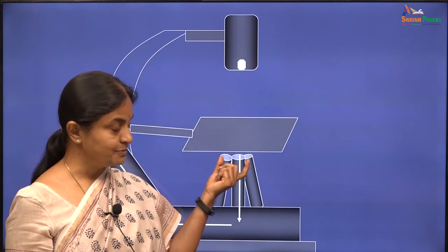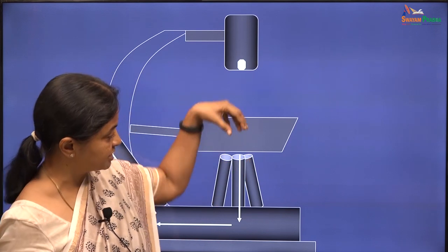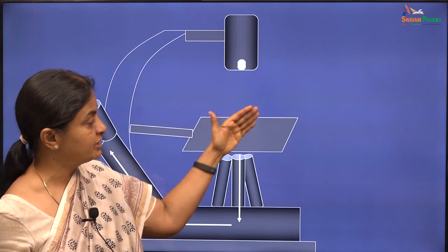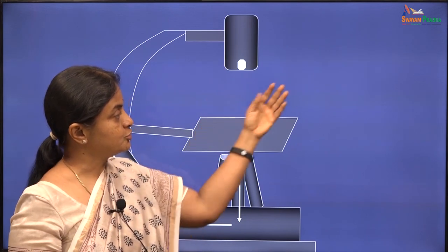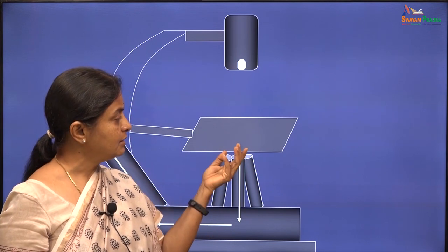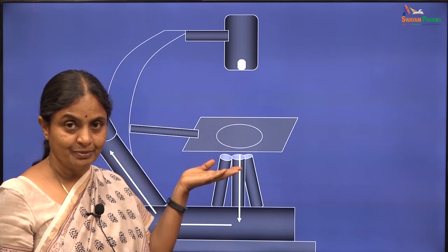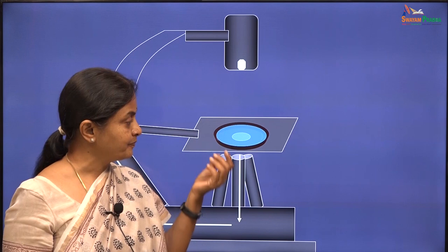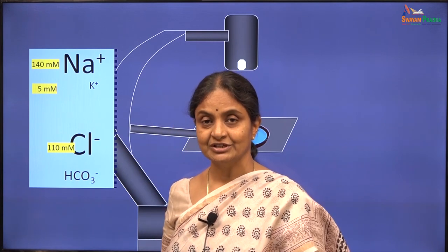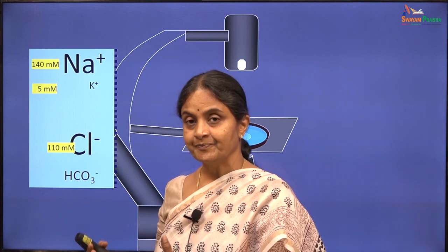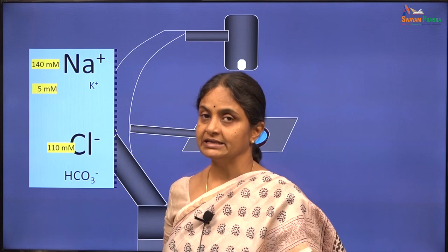In patch clamp technology, an intracellular electrode is placed on a cell under microscopic guidance using an inverted microscope, which is preferred because the objective is below the stage. In an ordinary light microscope the objective is on top and must be very close to the object, leaving poor working distance. With the objective below and the light source above, there is a good working distance to bring an electrode to the cell. Cells sit in a dish on a transparent area of the stage, bathed in extracellular fluid resembling plasma.